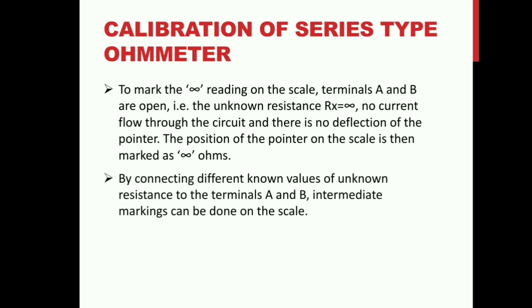The infinity mark is obtained when terminals A and B are open — no current flows and there is no deflection. By connecting different known values of resistance to terminals A and B, intermediate markings can be done on the scale, so the scale can indicate values between 0 and infinity.